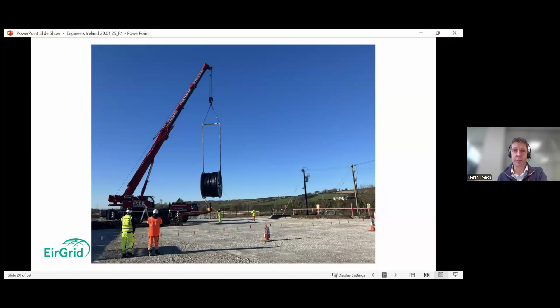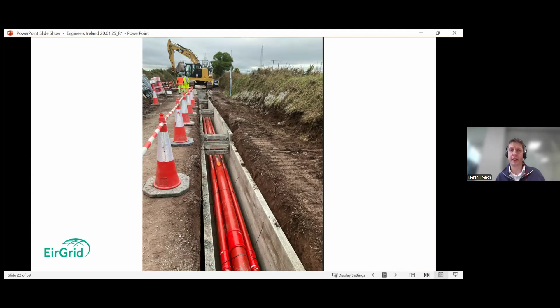This is an image of the AC trench that was being installed on the road outside the existing Knockraha substation. The 400 kV cable is installed in a ducted system, in a trefoil configuration, think of a triangular configuration with 2 at the bottom and 1 on top, with 2 telecom ducts also installed for the fiber optics in the same trench. So a narrow enough trench, but you can see the scale of the roads we're dealing with here. Narrow roads often required road closures to undertake the works and activities.